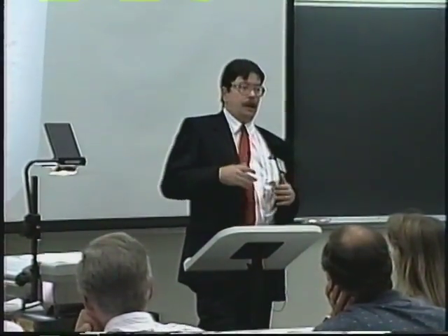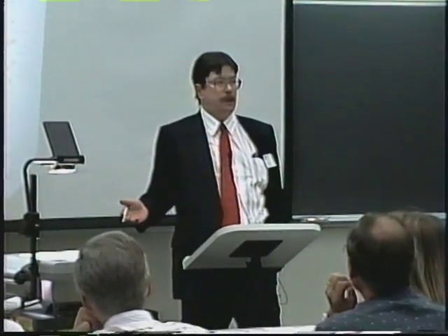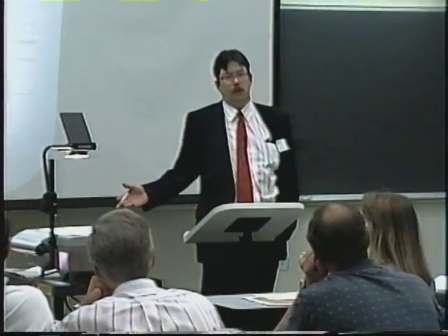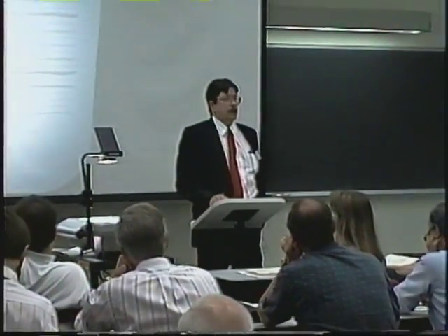I was just wondering why you took the voltage readings instead of just direct absorbance, but if you're doing atomic absorption. Well, the one that I showed here was actually a colorimetric analysis. It's a Technicon auto-analyzer system, so it was designed in the 50s. It feeds a strip chart recorder. We have a total organic carbon analyzer that feeds a digital integrator, gives us a result. We don't like the result, so we do another regression on it. So we're doing a second order regression then.